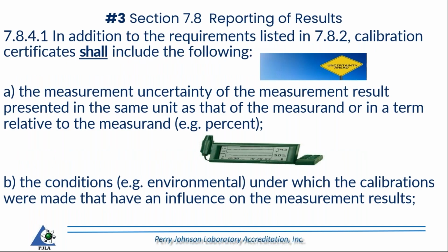Now, 7.8 is specific to calibration. So we have "shall" there. So that's a requirement. Measurement uncertainty, that is a requirement. It has to be reported.